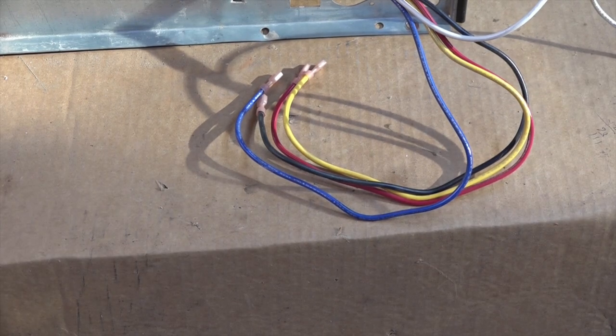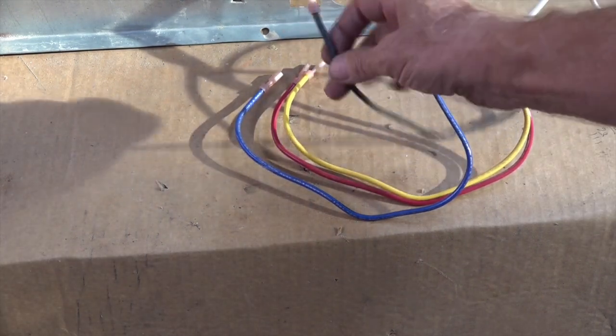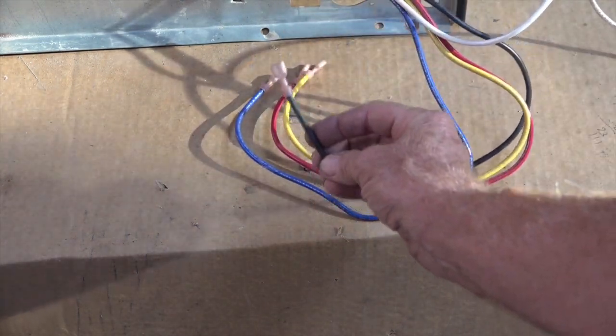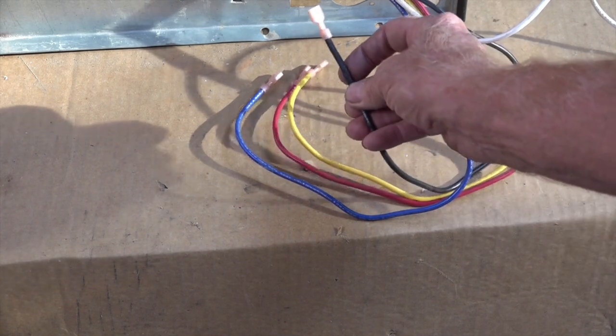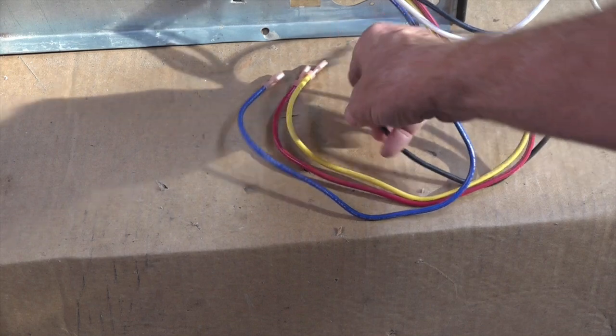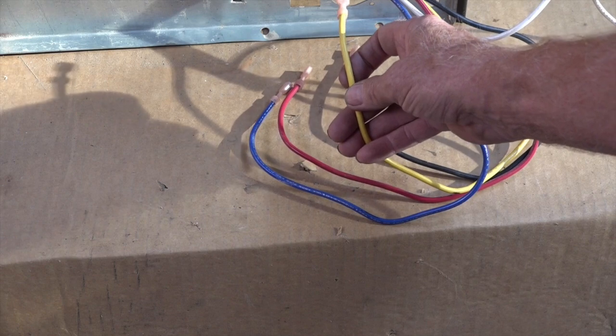Which one's which? Well, the shortest winding is the high speed, that's this one right here. And it's black. That's the shortest winding. The yellow is medium high, it's a little longer winding.